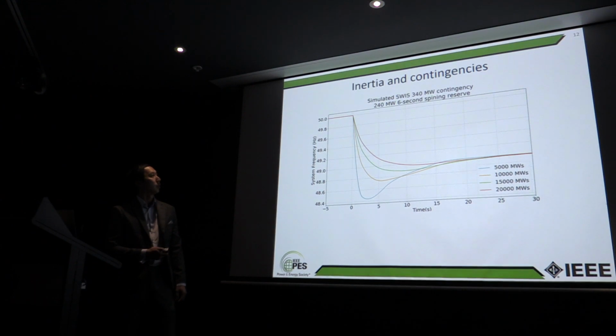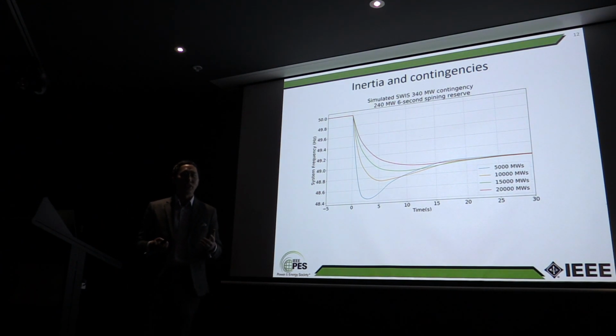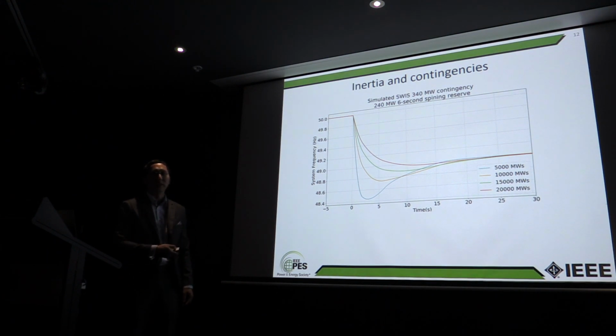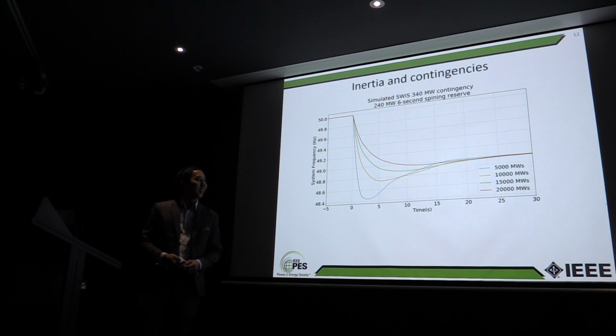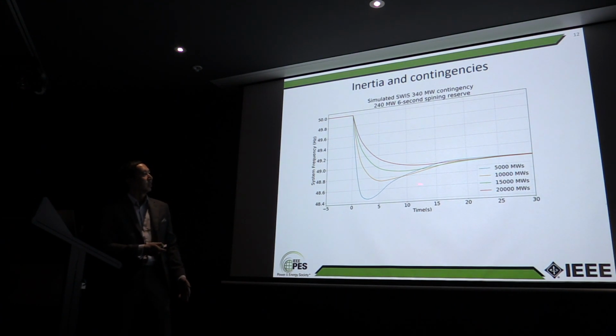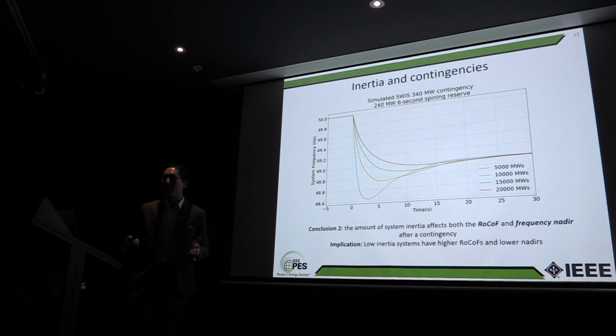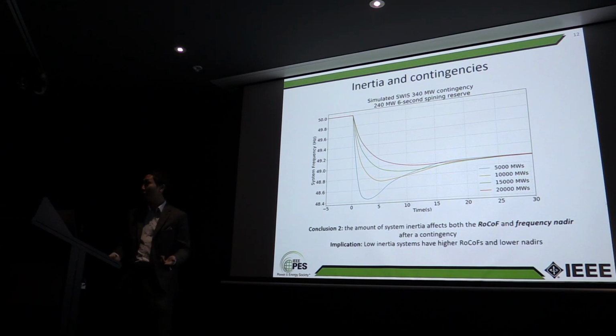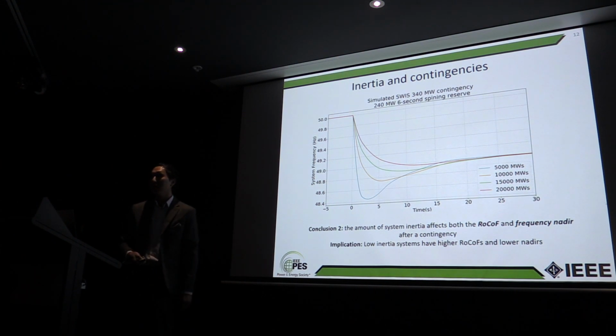So here are some simulated curves. This is pretty hypothetical, so don't take too much stock of the numbers here. It's not real. But you can really see that when you have very low inertia, you have a very high RoCoF. So it drops off very quickly. And the frequency nadir, or the minimum frequency, is also much lower. And they steadily go up, and the RoCoFs start going down as you increase the amount of inertia in the system. So the second conclusion here is that the amount of inertia really does affect both the RoCoF and the frequency nadir. And that low inertia systems have both higher RoCoFs and lower frequency nadirs.